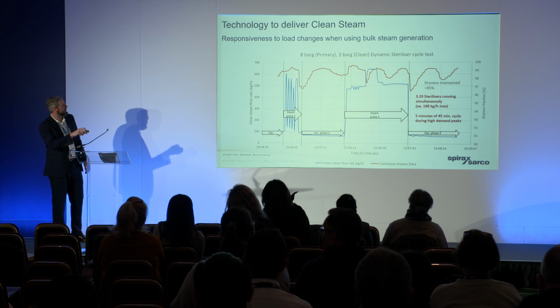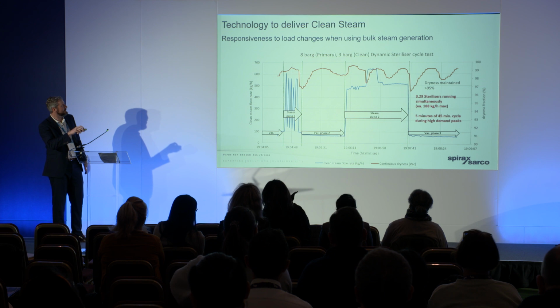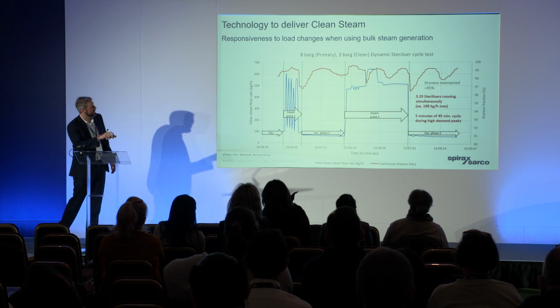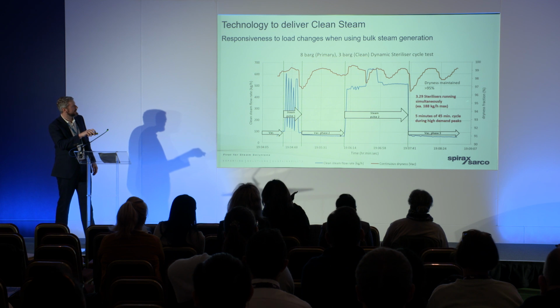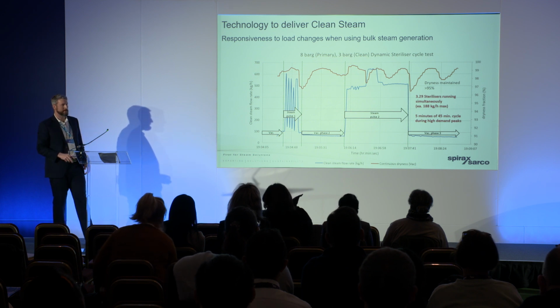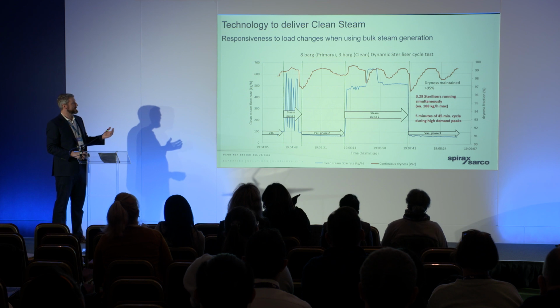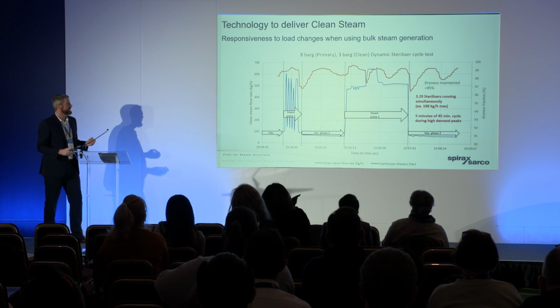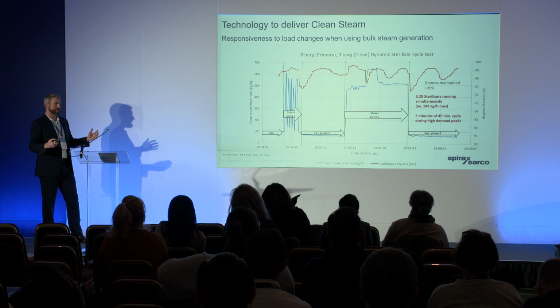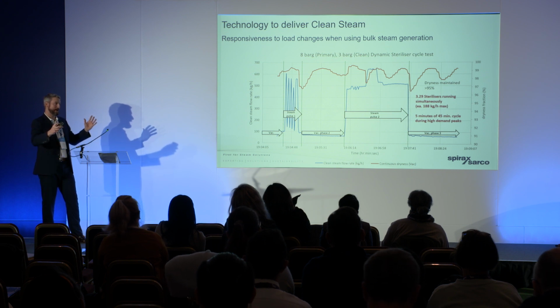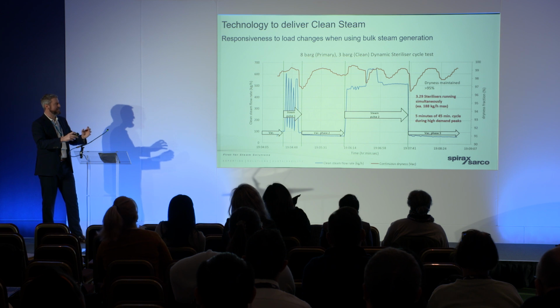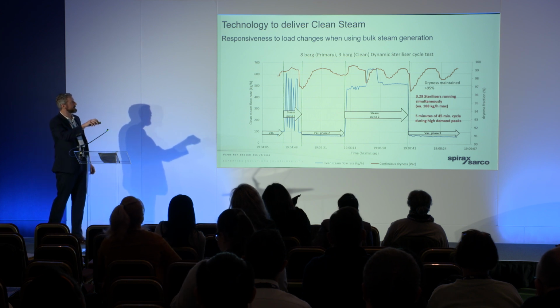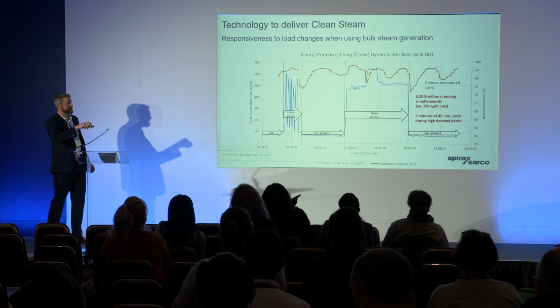And you can see here that where we had the high spikes in steam demand, you can actually see the steam quality drop off. Can you see after the high demands? We were still able to stay within 95, which is this here, look. So we were able to prove that we could do that with our clean steam generators. But what it does really indicate is that that was with a high volume of steam, with reservoirs of steam in the pipework. If you would scale this down, I should imagine these drop-offs in steam quality would be much more exacerbated.